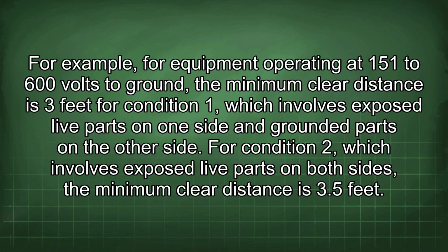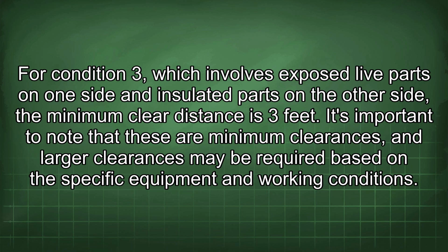For condition 2, which involves exposed live parts on both sides, the minimum clear distance is 3.5 feet. For condition 3, which involves exposed live parts on one side and insulated parts on the other side, the minimum clear distance is 3 feet.